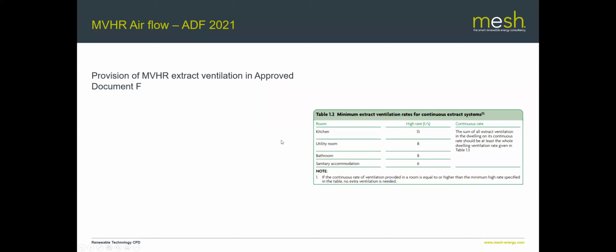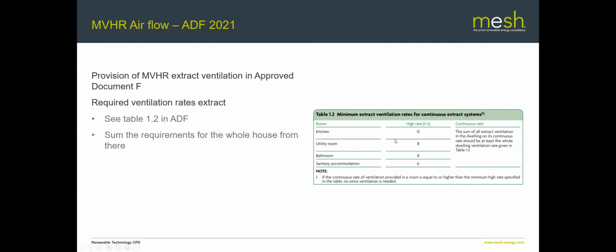So what about extract? Well, extract is also given, and it's expressed in terms of the amount of air that you must extract from each particular room. But you've also got the other criteria, which is you should try and meet the supply air. And in most cases, you end up having to extract slightly more than these minimums. But these are the minimums given in the document. So for a kitchen, you must extract at least 13 litres per second continuously. In a utility room, that drops down to 8. Same for a bathroom, and for a WC it's 6.